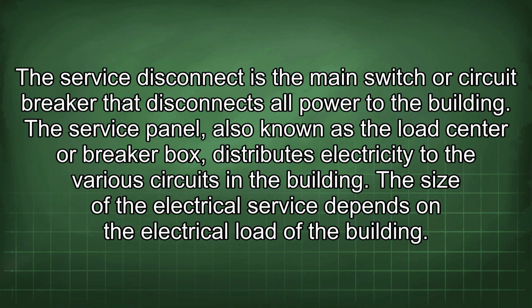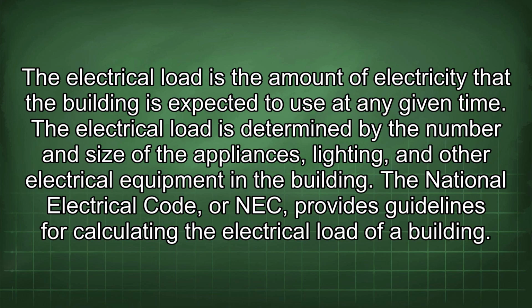The size of the electrical service depends on the electrical load of the building. The electrical load is the amount of electricity that the building is expected to use at any given time. The electrical load is determined by the number and size of the appliances, lighting, and other electrical equipment in the building. The National Electrical Code, or NEC, provides guidelines for calculating the electrical load of a building.